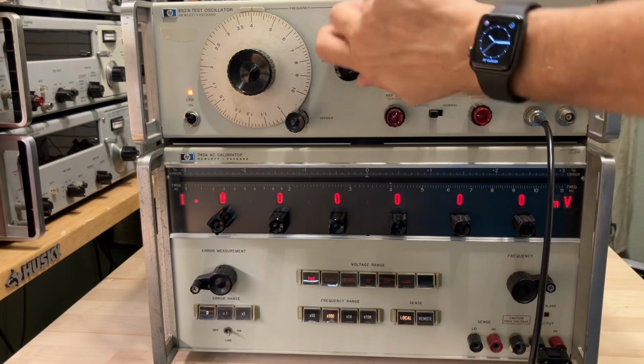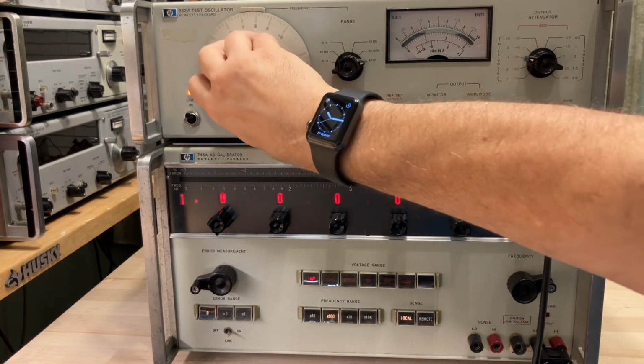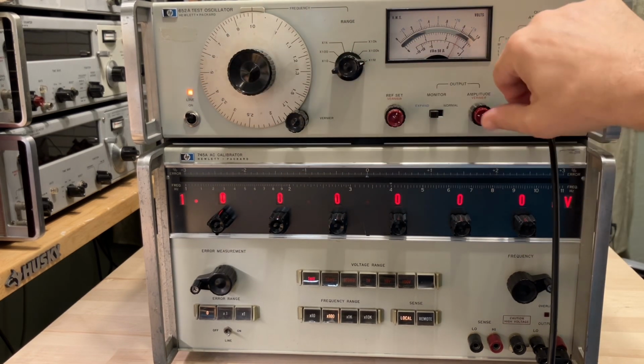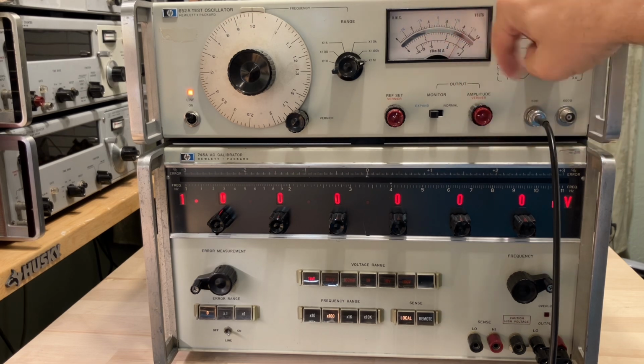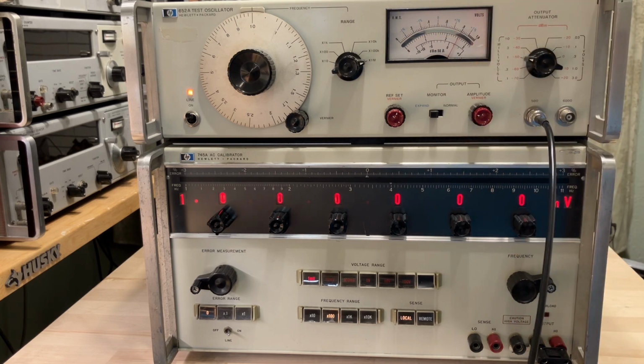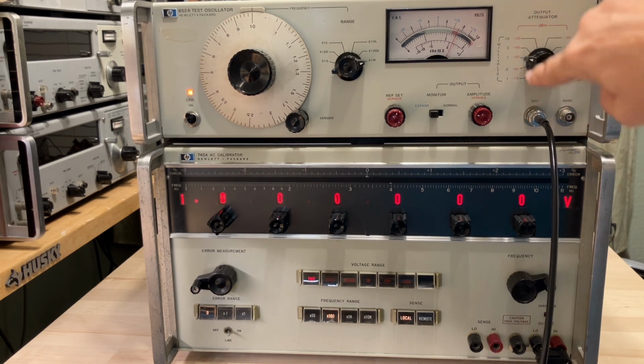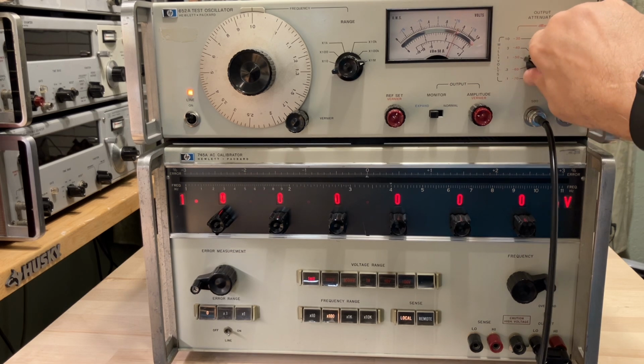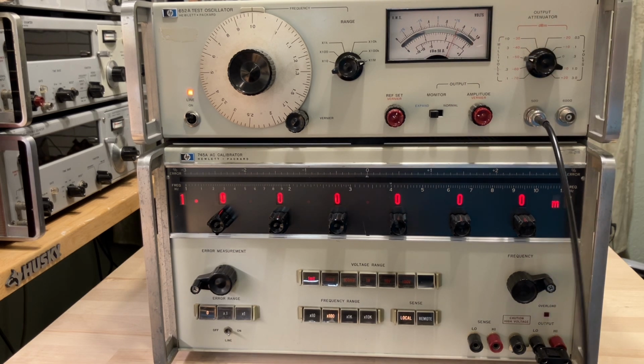Then I can adjust the frequency up to as high as 10 megahertz, readjust the amplitude so that it matches, and test the frequency response of my 400H under test. I can continue that with each amplitude range in this instrument. So I've tested all of the ranges and all the frequencies, and tested the entire instrument.